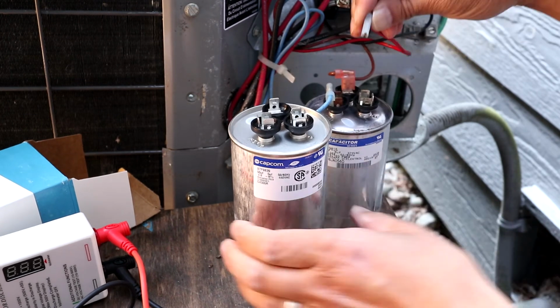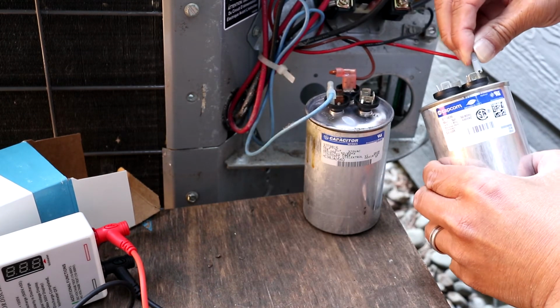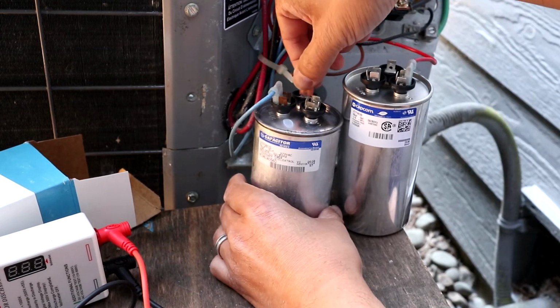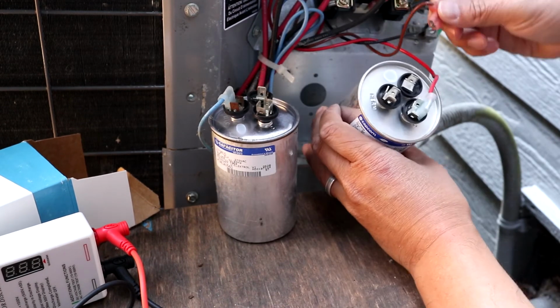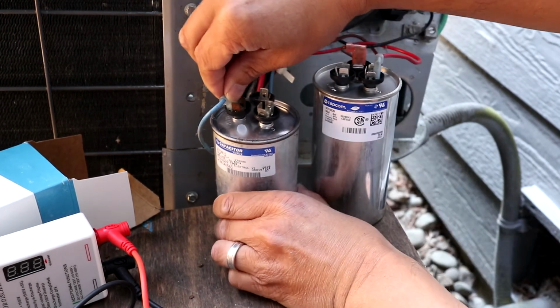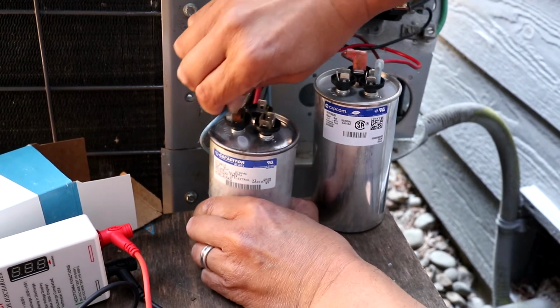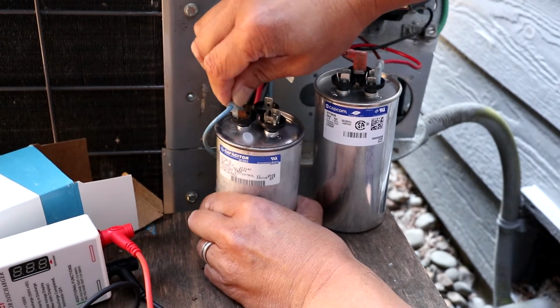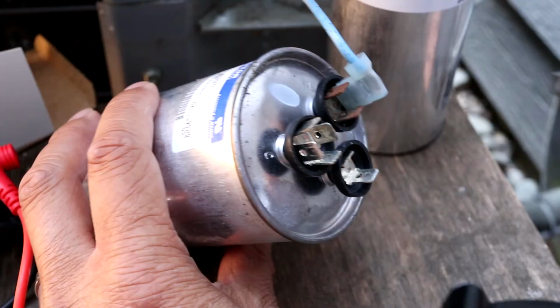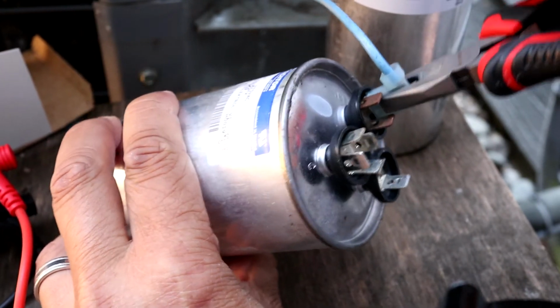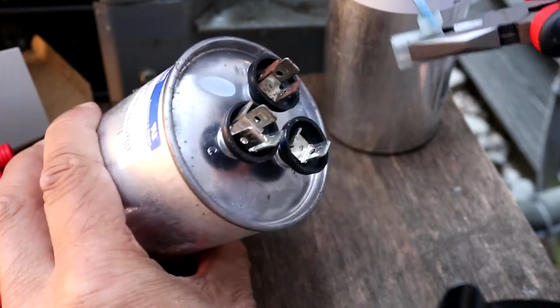Wiring is easy to do if you do it one at a time. C to C, HERM to HERM, and fan to fan. If you find that any of the connectors are stuck, use a pair of pliers and pull it off from the connector and not by the wire.